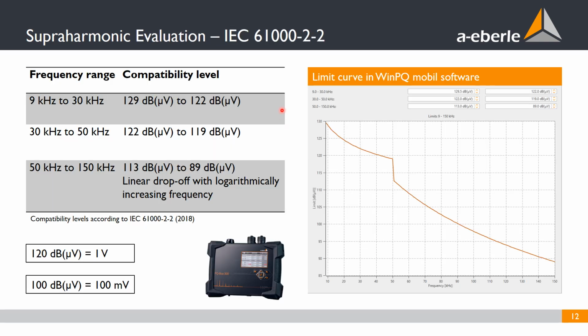In general, at the moment, there's only one grid standard regulating these higher supraharmonic frequencies, which is the IEC 61000-2-2. And you can see here an extract of the standard with the disturbance levels. It's a bit hard to read because they are defined in dB microvolts, so I placed a little hint here. 120 dB is about 1 volt. So you can imagine that, for example, at 30 kilohertz, the limit value is about 1 volt, and it's dropping down to below 100 millivolts at 150, and this is how this limit curve would look.